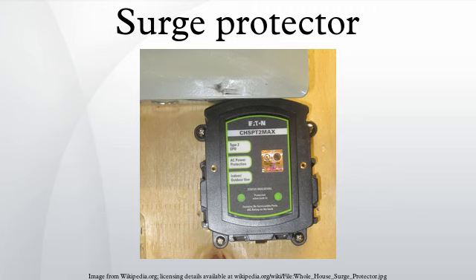It can dissipate power continuously, and it retains its clamping characteristics throughout the surge event, if properly sized. Carbon block spark gap over voltage suppressor. A spark gap is one of the oldest protective electrical technologies still found in telephone circuits, having been developed in the 19th century. A carbon rod electrode is held with an insulator a specific distance from a second electrode. The gap dimension determines the voltage at which a spark will jump between the two parts and short to ground.